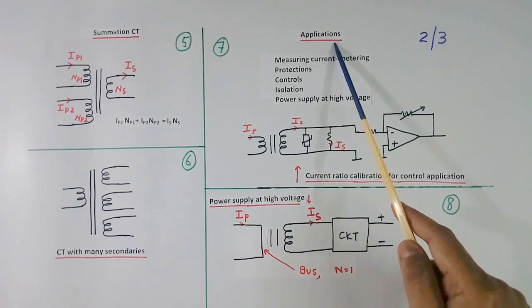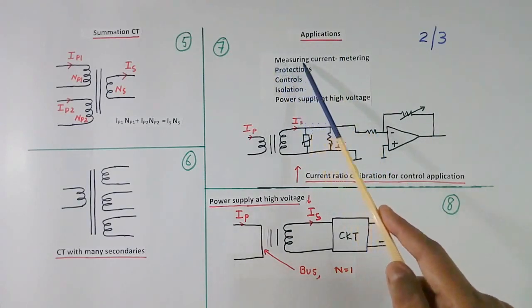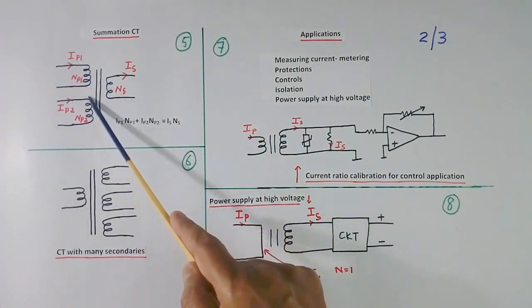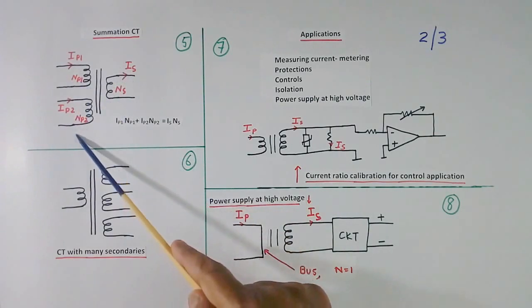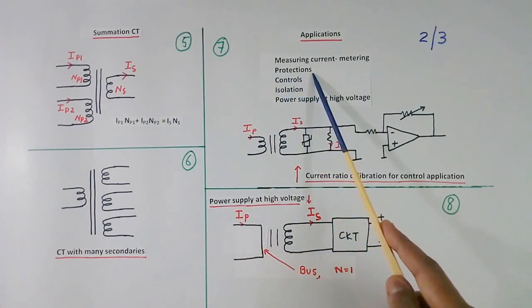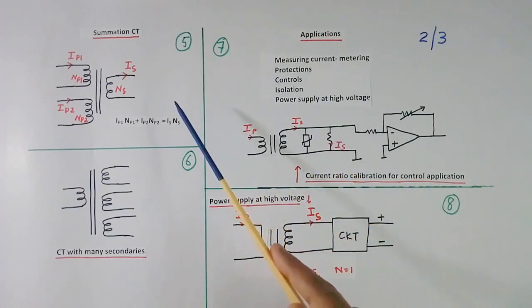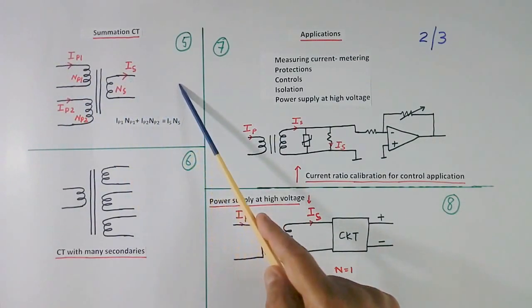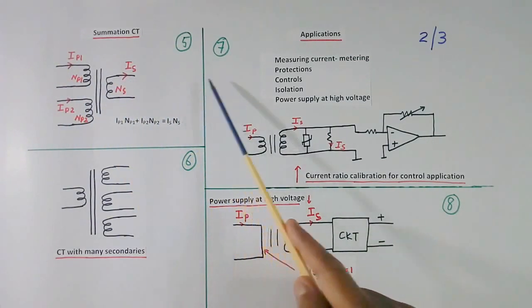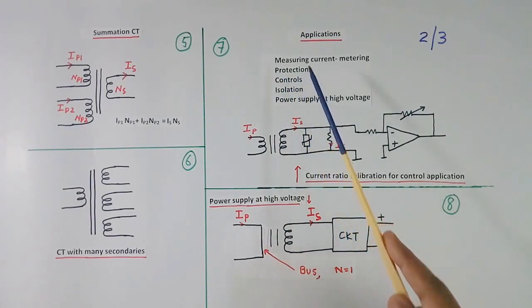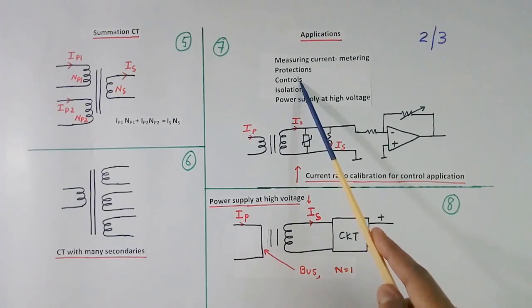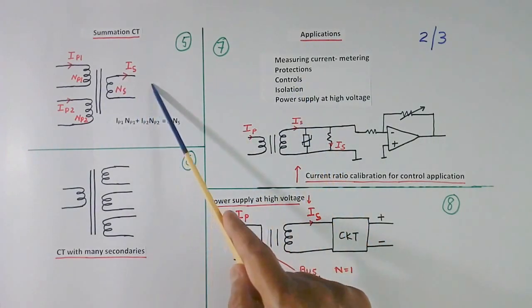Now we come to applications. First application is measuring current metering. We connect 1 ampere meter here. It will indicate the current flowing in the primary or sum of the primaries. Second is protections. Sometimes we have to protect the system from over current or under current here. So this will go to one protection relay. That protection relay will protect the system. Now controls. Suppose you want to control power factor or some other parameter. So the CT output will go to control.